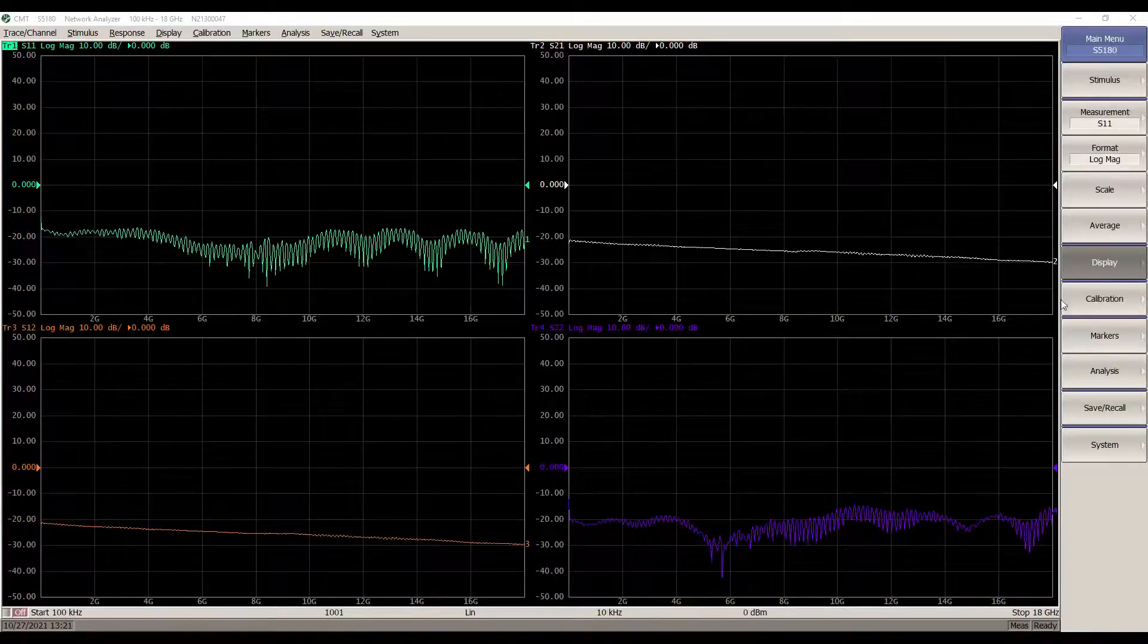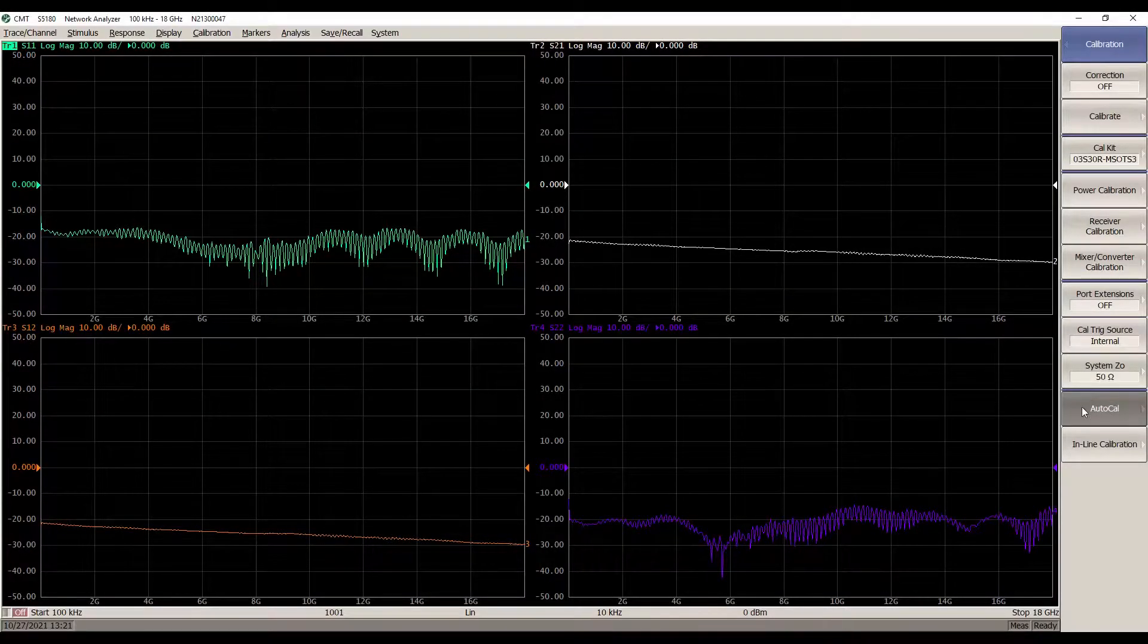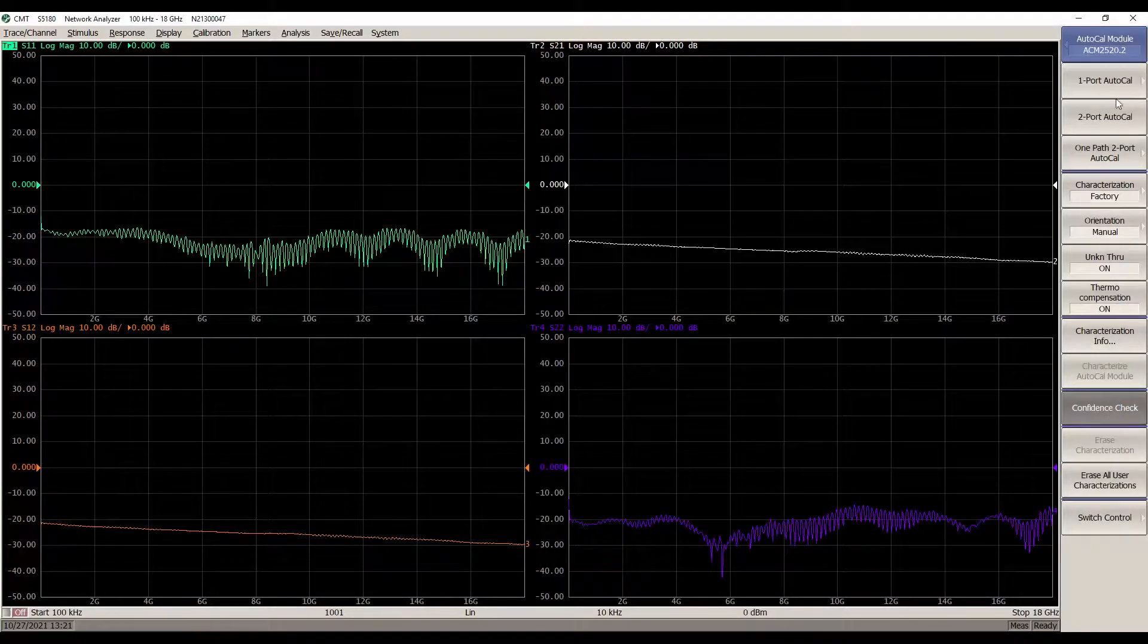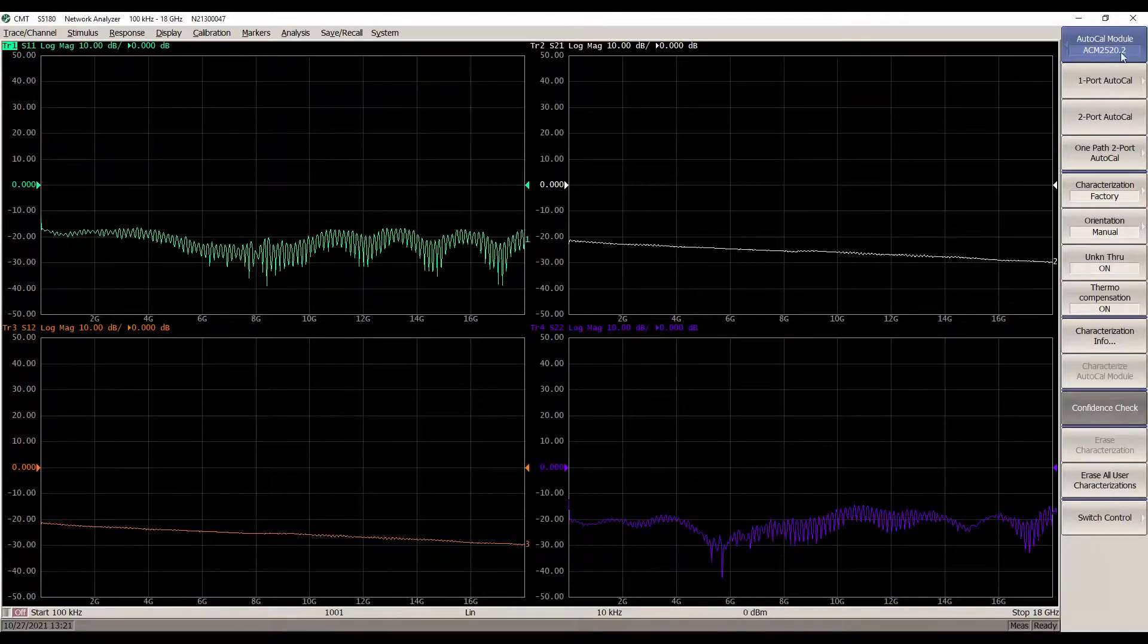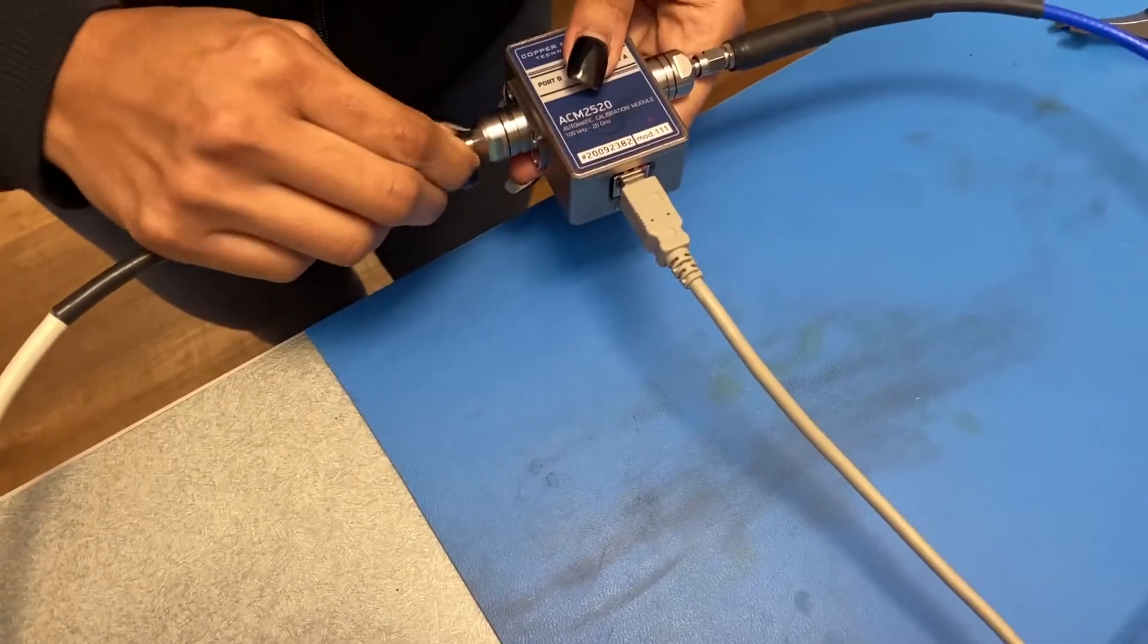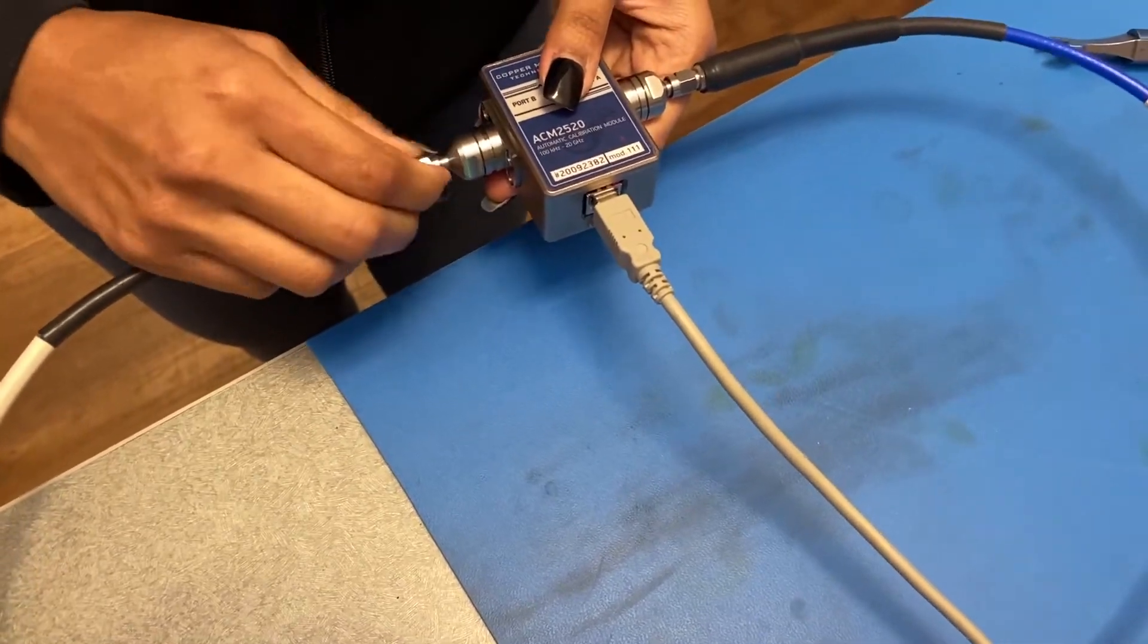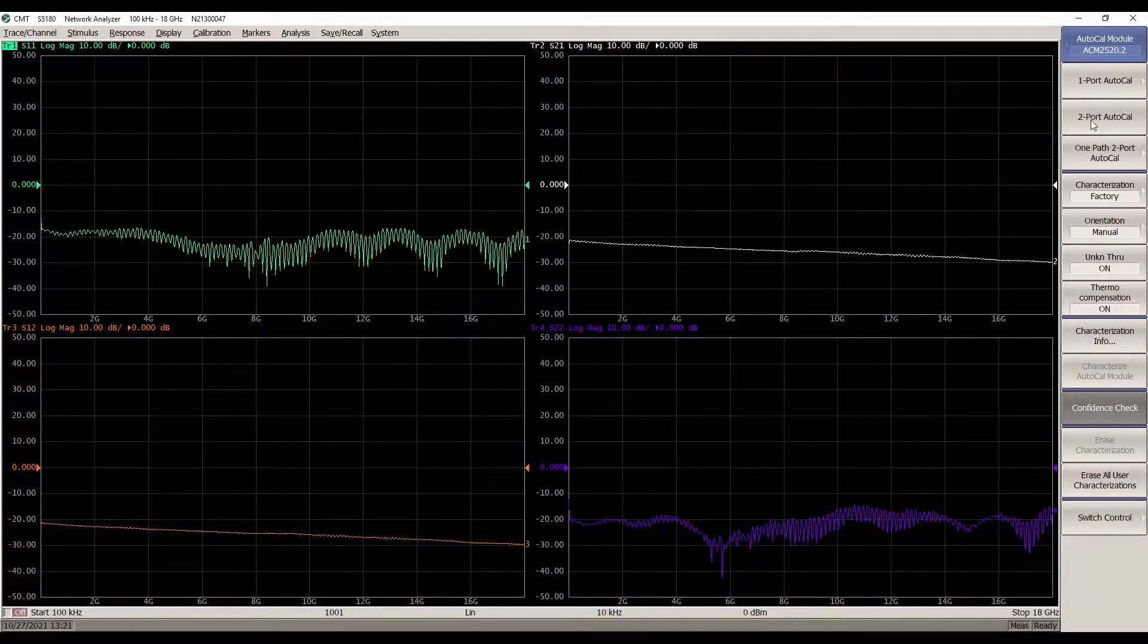Then navigate to Calibration, Auto-Cal. The Auto-Cal module is automatically recognized by the VNA application. Now connect the ACM to the VNA ports using cables and perform the required calibration.